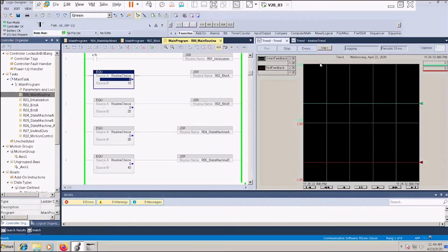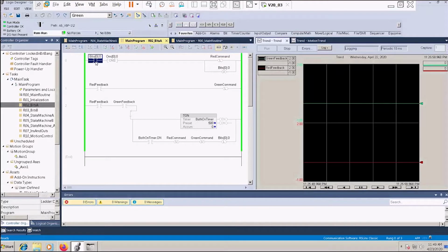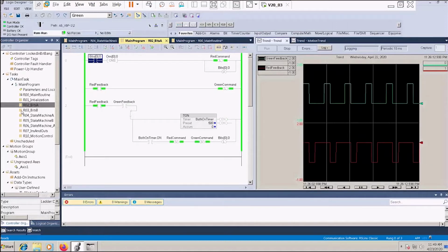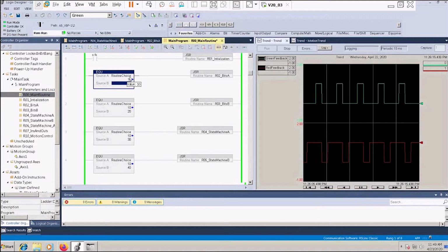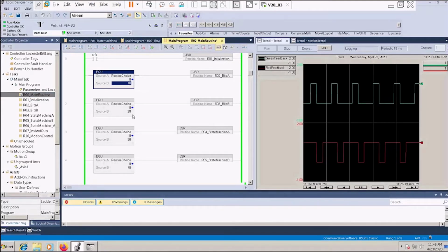I'm utilizing trending, which is very useful in general, and even more useful with motion. For trending, actual position, command position, actual velocity, position error, all sorts of tags, throw them up on a trend, and then you can visualize what is happening with your particular axis. So let me enable our bit code to run. We go to bits A and start it running. It produces some arbitrary waveform. It looks like red leads green, with different pulse widths, and so on. Okay, that's good. The machine is running. So bits work. Now, turn this off.